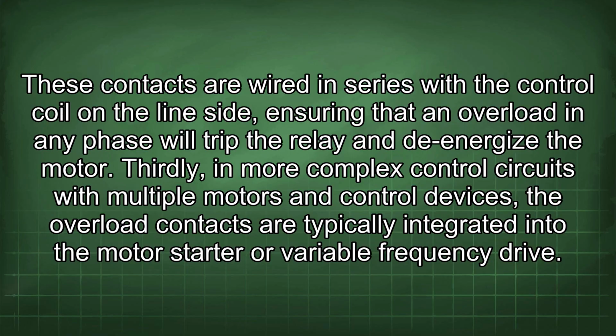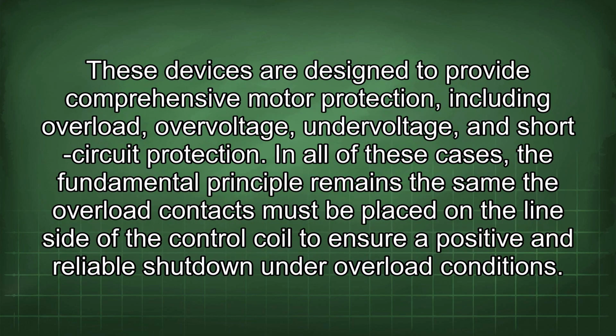Thirdly, in more complex control circuits with multiple motors and control devices, the overload contacts are typically integrated into the motor starter or variable frequency drive. These devices are designed to provide comprehensive motor protection, including overload, overvoltage, undervoltage, and short-circuit protection. In all of these cases, the fundamental principle remains the same: the overload contacts must be placed on the line side of the control coil to ensure a positive and reliable shutdown under overload conditions.